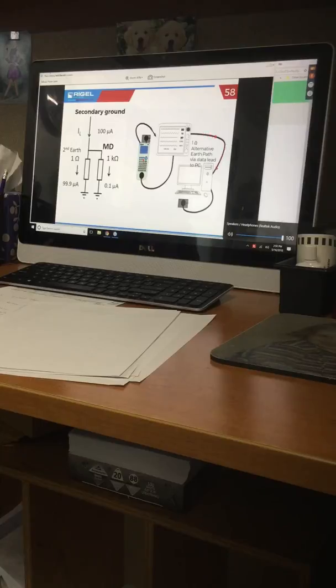So what we show here is a little diagram, two resistors in parallel, one being a 1 ohm resistor, the other being the 1K body model, and most of your current is going to flow through that second earth connection. Very little current will flow through the 1K body model, which just says then that perhaps you're doing a test and your result is inaccurate. Fortunately, safety analyzers, well, some, I'm not saying whose, but we are sponsoring this webinar. Anyway, safety analyzers will come up and give you a message to check for a secondary ground condition to make sure that you're getting a good accurate reading.